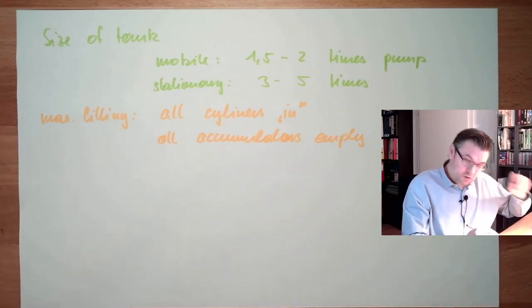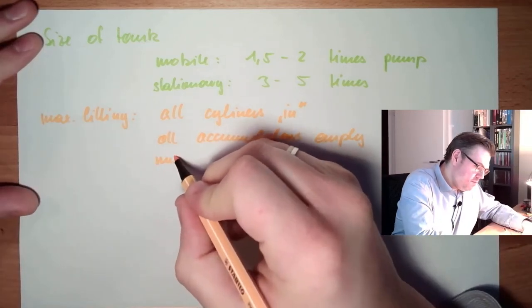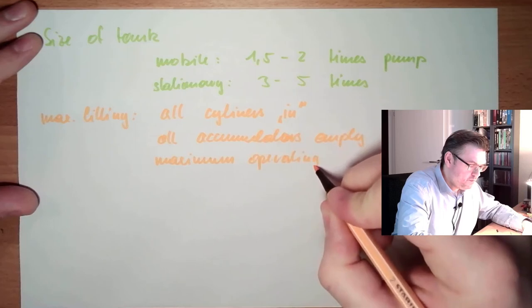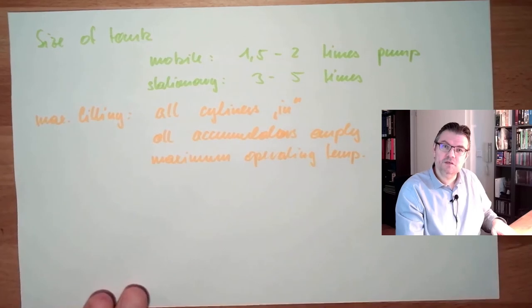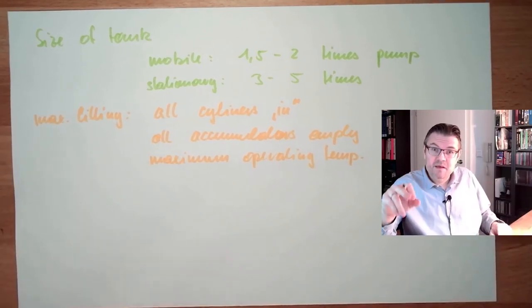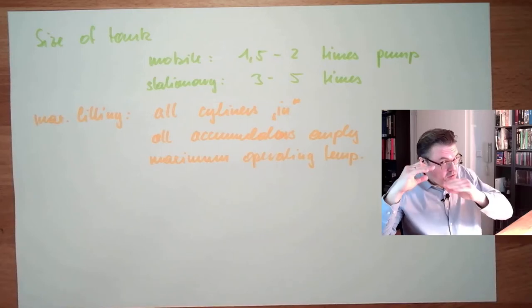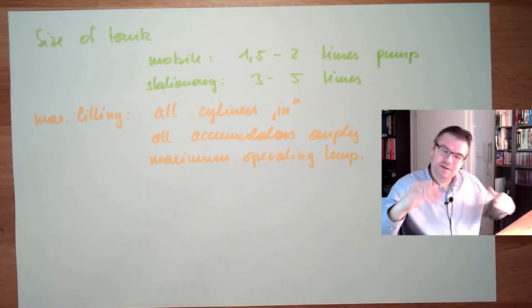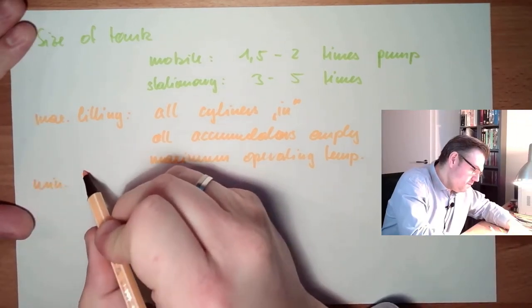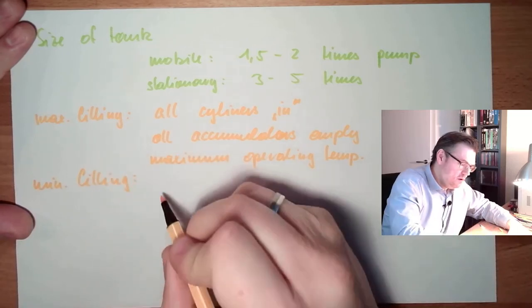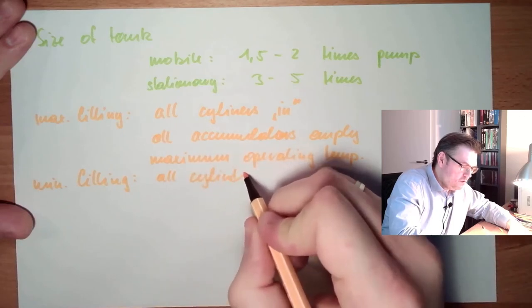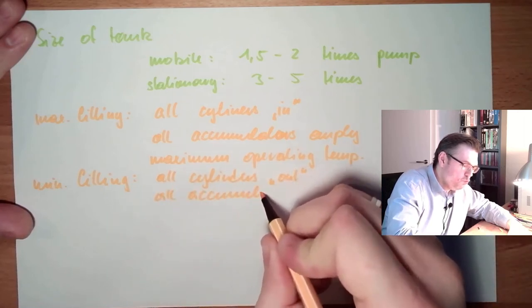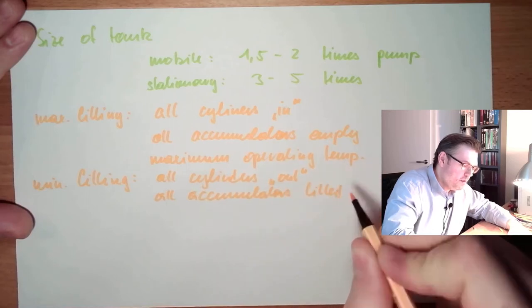Also all accumulators empty, and maximum operating temperature. If these conditions are met, I have the maximum filling. At maximum filling, the tank should still have some reserve, should not look like an infinity pool. Minimum filling is the opposite: all cylinders out, all accumulators filled, and minimum operating temperature.